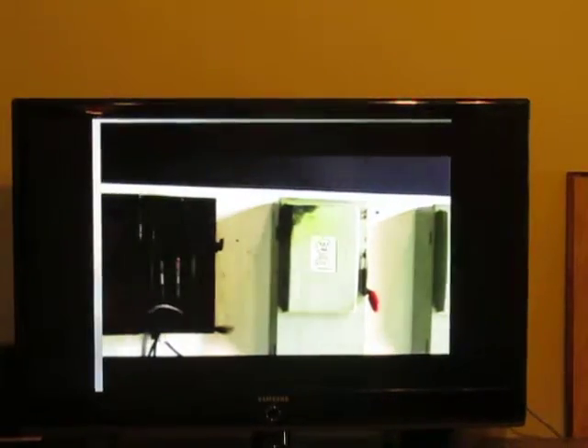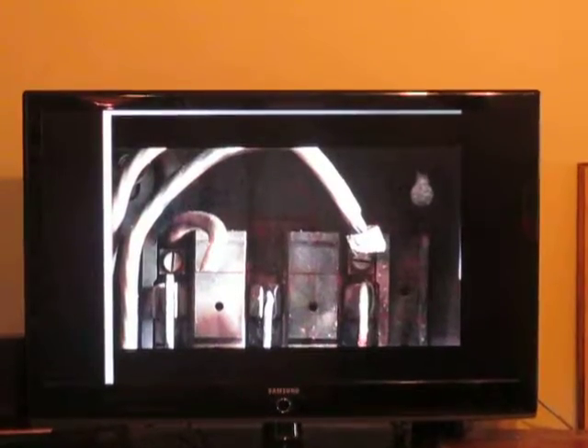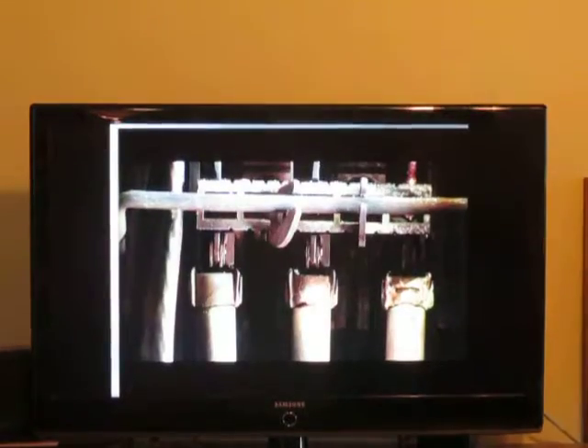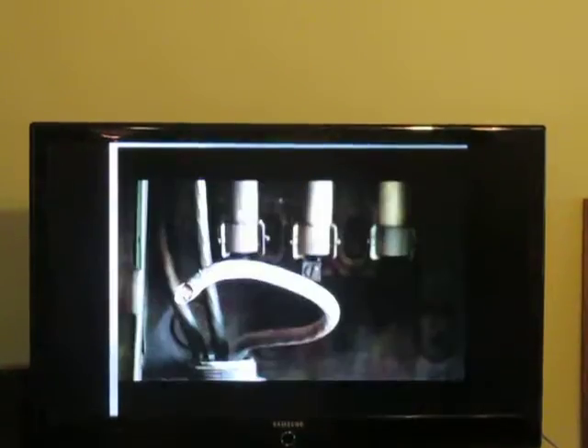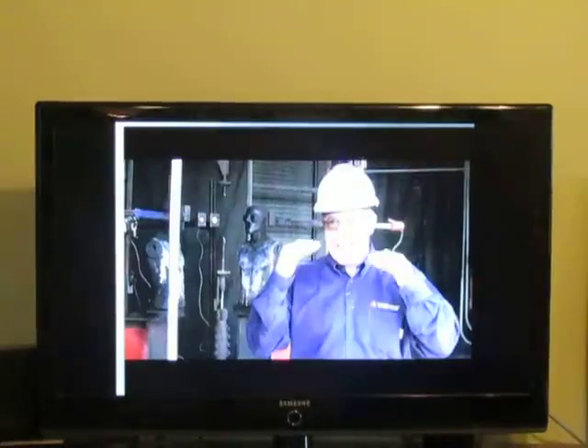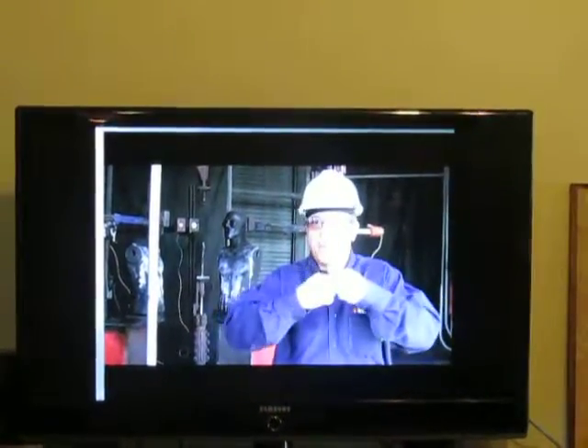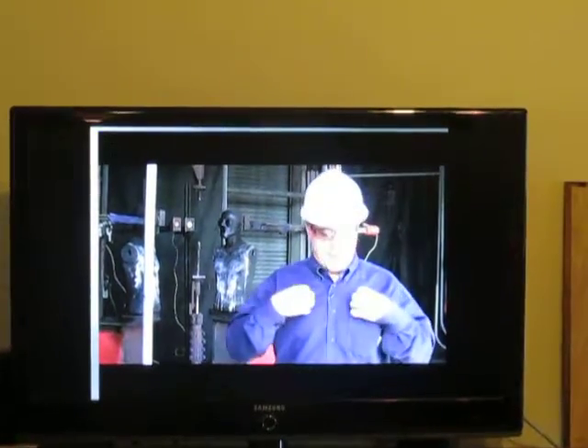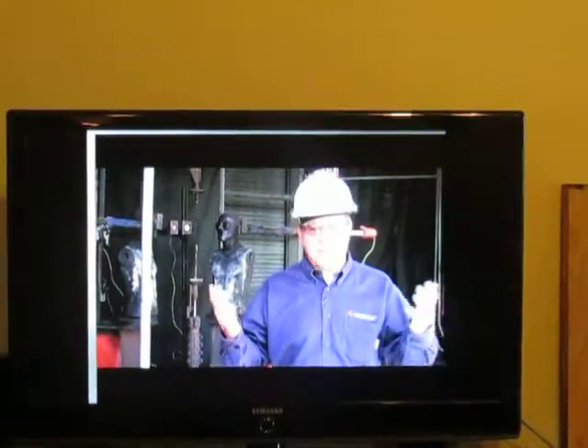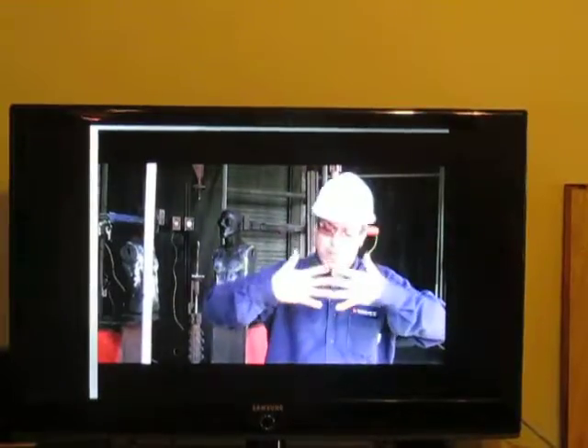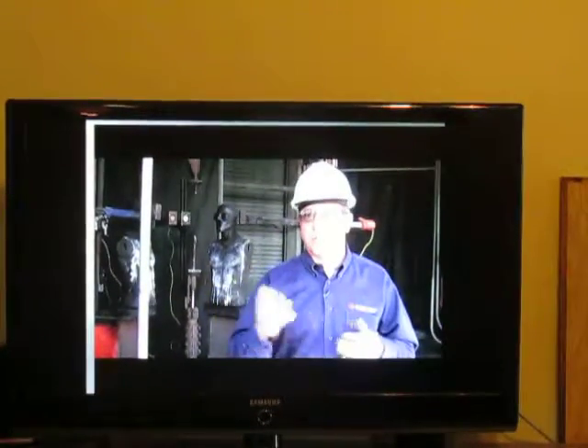Knowing the arc flash hazard of a piece of equipment allows for better protection. Simply wearing flame-resistant clothing is no longer enough. If you know the arc flash hazard is, let's say, 9 calories, then an 8-calorie shirt isn't sufficient. 8 is less than 9. You need to layer up. If you know the arc is 6 calories, an 8-calorie shirt is just fine. So this idea of matching the hazard to the protection is relatively new in arc flash.